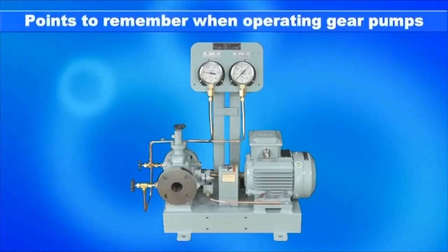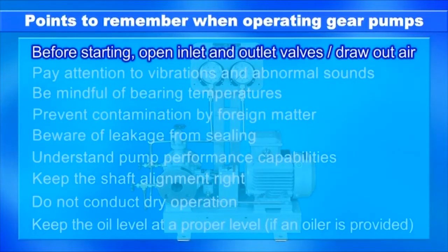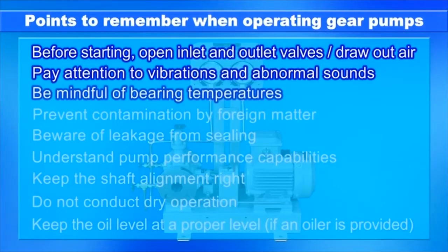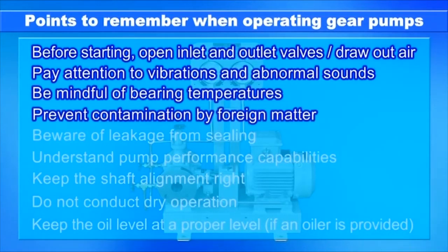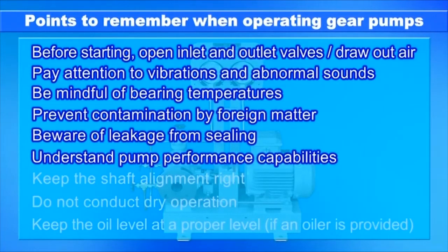The following precautions must be taken to operate gear pumps and conduct maintenance: open inlet and outlet valves before starting the pump, draw out air before starting the pump, pay attention to any vibrations and abnormal sounds, be mindful of bearing temperatures, prevent contamination by foreign matter, be aware of leakage from sealing, and understand pump performance capabilities.